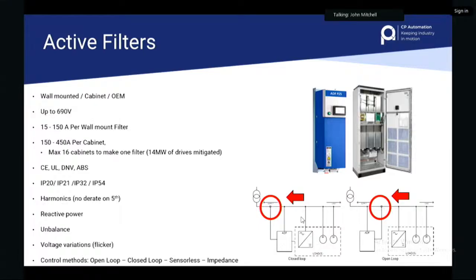Products like this are a prime example. We partner with two manufacturers, Comsys and Revcon. This is the Comsys filter - very comprehensive, robust, with amazing software, and it can also stop issues with resonance and other things because it has impedance control. EV chargers, for example, can be quite problematic to mitigate harmonics from, and we can do that easily with this product. They go up to 690 volts, so these are LV connection products.